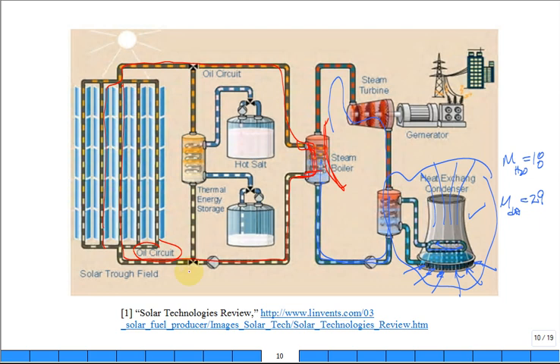Now let's take a look at storing the thermal energy. When the sun is really hot, maybe it's making so much hot oil, you can divert some of the hot oil down to another heat exchanger where the oil is going to be cooled and hot salt or cold salt coming out of here becomes hot on this top side. So the salt, maybe it started with a full tank of cold salt. And as you want, you transfer the salt to an upper tank and it fills up that upper tank as the level in the lower tank goes down. And now you have a tank full of hot salt.